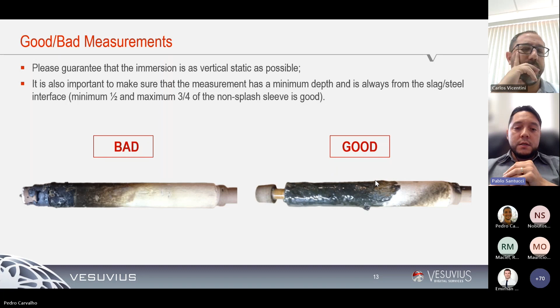And here is another good practice that we also recommend, which is to consider the Sievert's law for these hydrogen readings. Sievert's law is basically what tells us which element can contribute or not in terms of hydrogen pickup during that measure. But not only that, Sievert's law can also consider the actual temperature of the steel as well as the referred immersion depth of our probe. So all of these factors can contribute to a better and optimum hydrogen number right after the measurement.